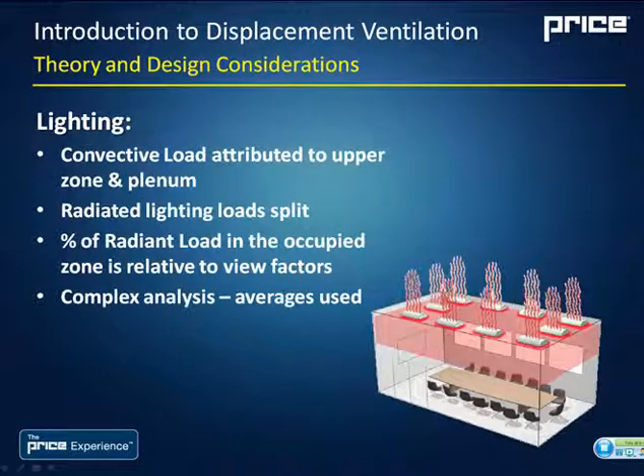The second component to the loads is lighting. As I mentioned earlier, the convective load is pretty well entirely attributed to the upper zone and plenum, so all the convective load from lighting is basically staying at the ceiling. We're not mixing it back down as we would with a mixed system. And then we have the radiant load, which is split between the upper zone and the lower zone, and it's also split depending on view factors and the types of surfaces in the room.